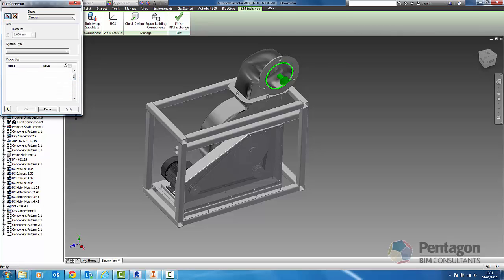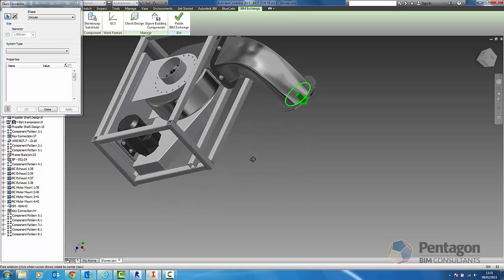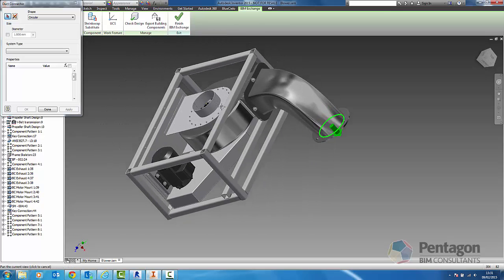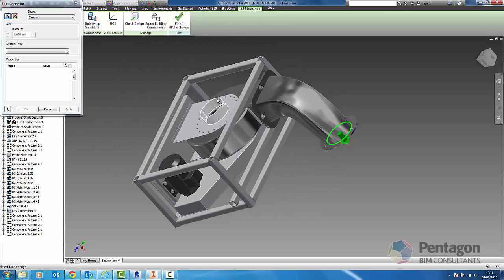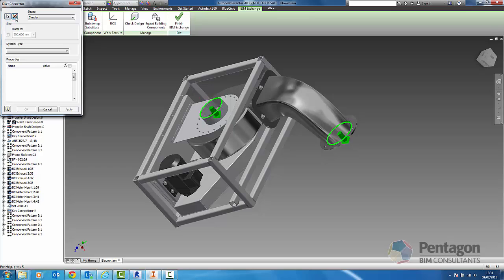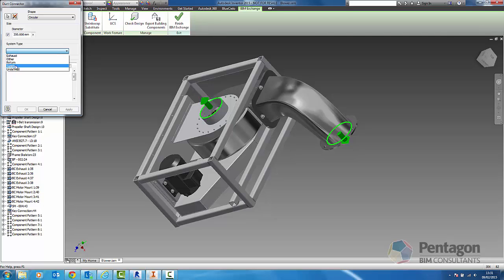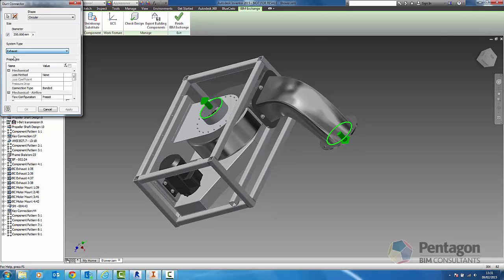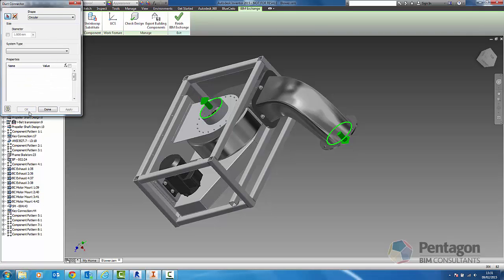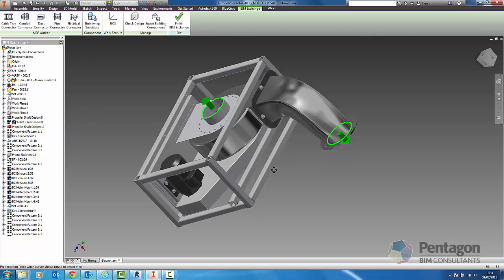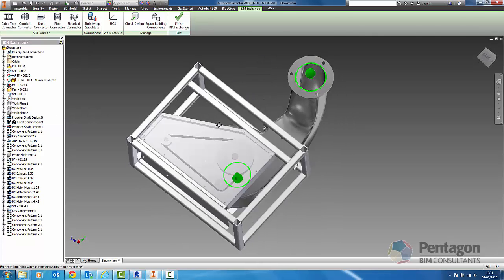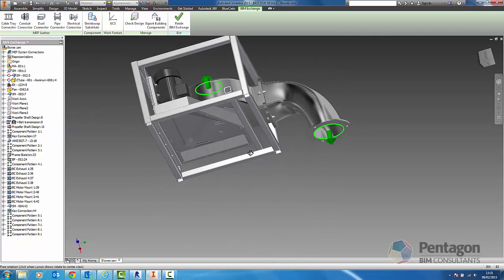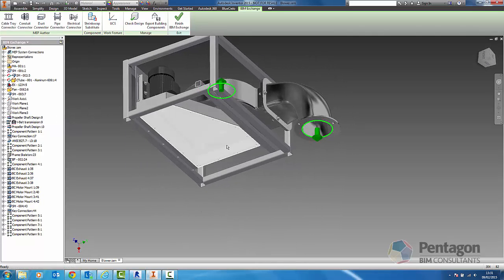I can apply that and then I can orientate it around to the rear of the design. We can flip the direction of the actual arrow there and we're just going to change that diameter. We're going to keep that 200 and we're going to say that's actually the return or the exhaust. We can hit apply and okay. We've added these connectors in and these connectors will come across in Revit and pick up the actual sizes.